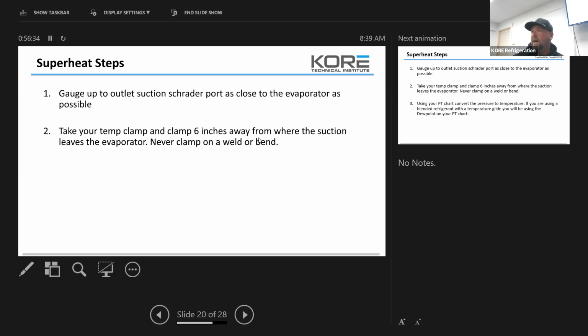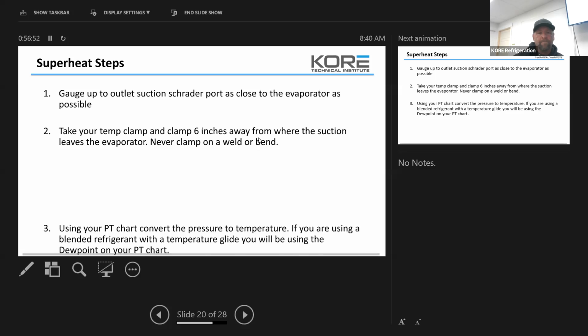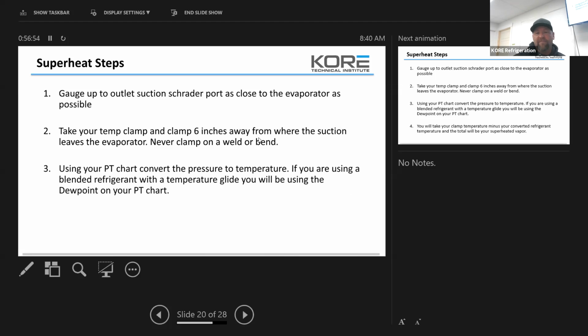I don't want to see somebody take a Velcro strap and strap a K thermometer to it. It just doesn't give you a good enough reading to really calibrate. This is a finite adjustment. It takes a lot of time and it takes finesse. If you're going to do this, you need to make sure you have the right tools. Use your PT chart, or the app on your phone, I don't care how you do it, but you need to understand converting that pressure to temperature and looking for the difference between your temperature and your pressure.